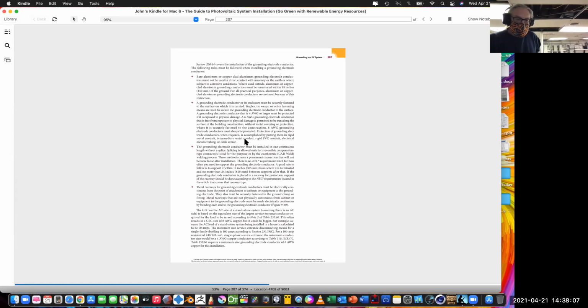So we want to make sure that we have a solid ground, our own ground, at 25 ohms or less. And if we need to add more than 1 grounding electrode to do that because we're in rocky soil, then that's what we're going to do, because those electrodes only cost $10, don't they? So stick them in the ground and put several of them.